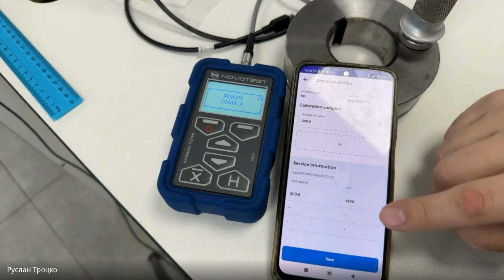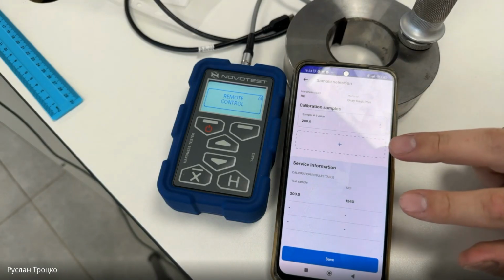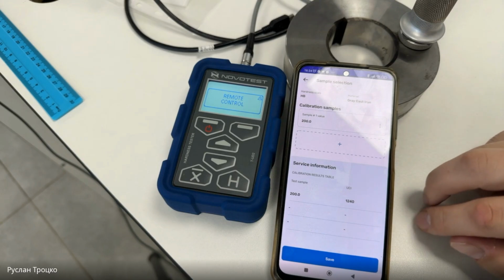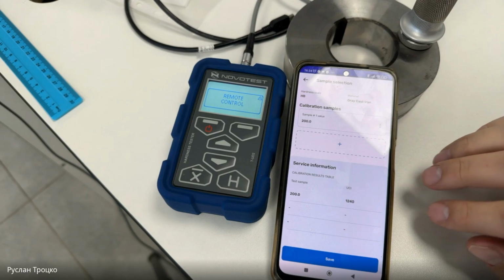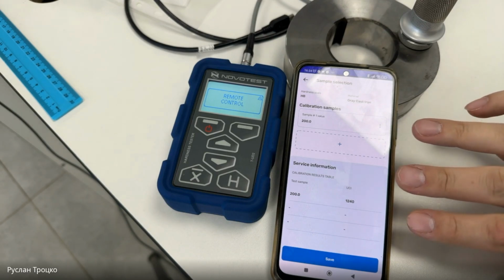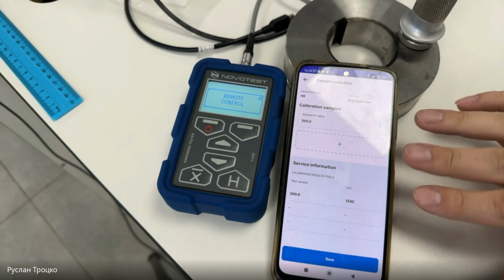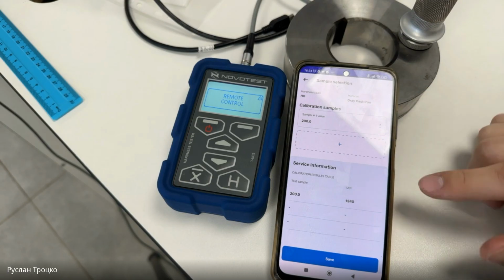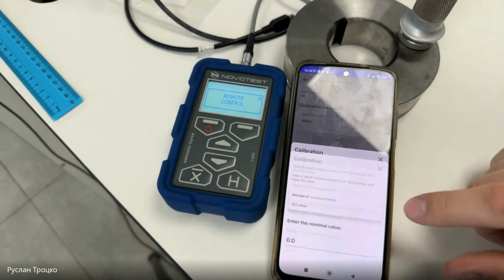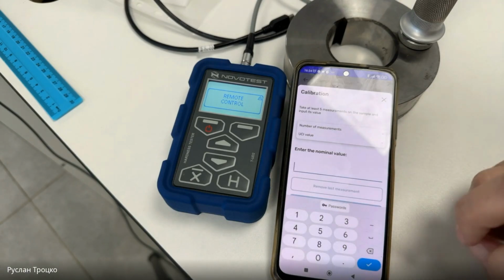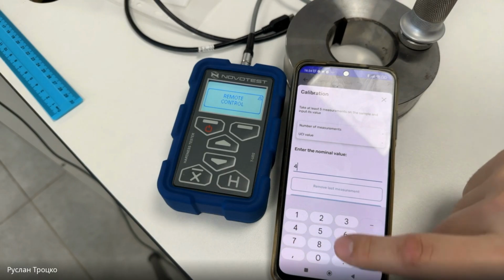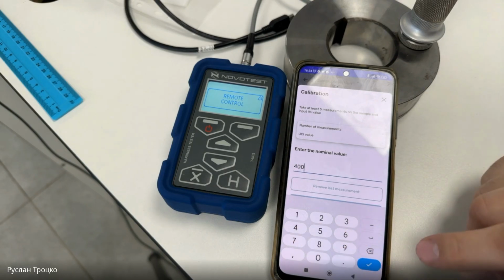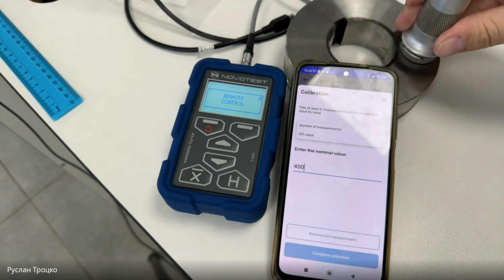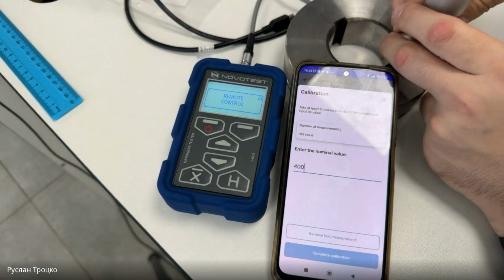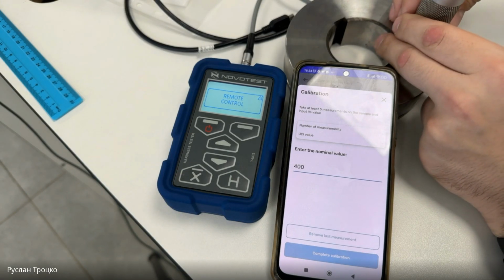And you need to do this 2 more times, because you always need 3 samples. You need to have 3 calibration samples for the first calibration. So we need to repeat this process again. I add my second calibration sample, for example, 400. This is 400 HB. I need to do 5 measurements again on the new sample.